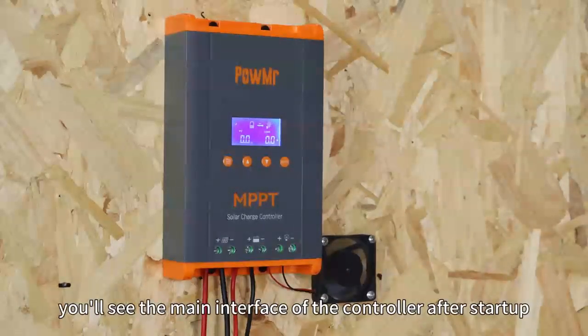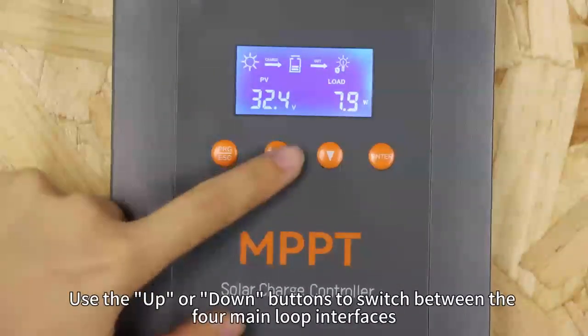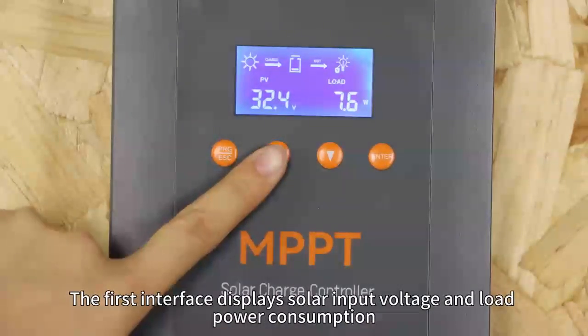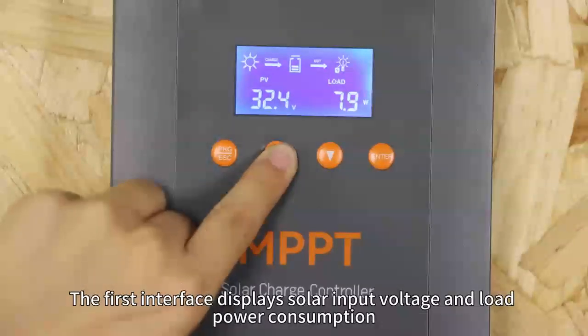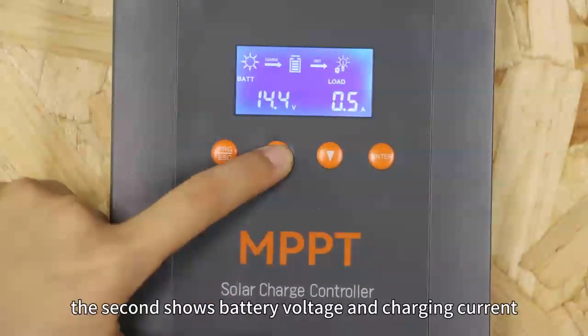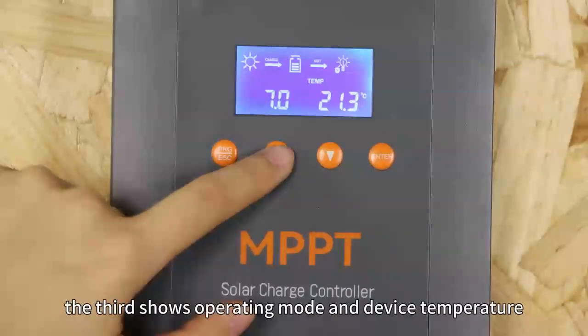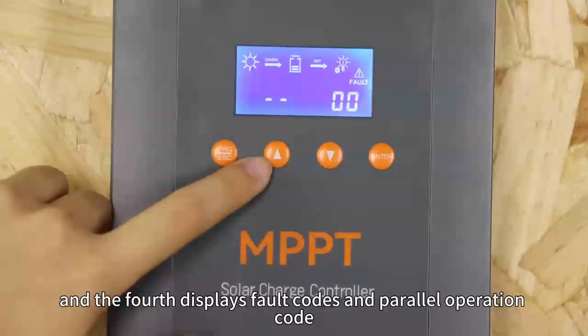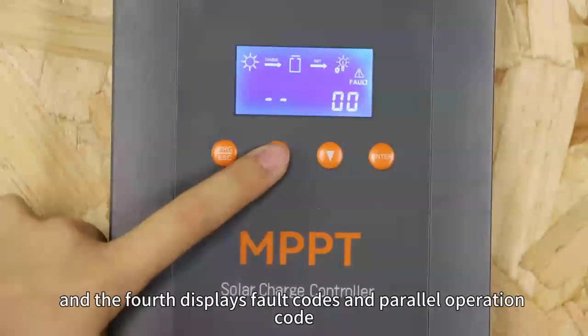You will see the main interface of the controller after startup. Use the up or down button to switch between the four main loop interfaces. The first displays solar input voltage and load power consumption. The second shows battery voltage and charging current. The third shows operating mode and device temperature. The fourth displays the fault code and the parallel operation code.